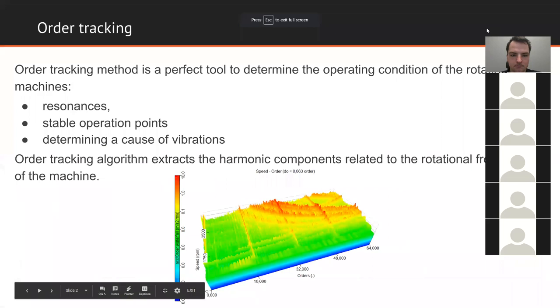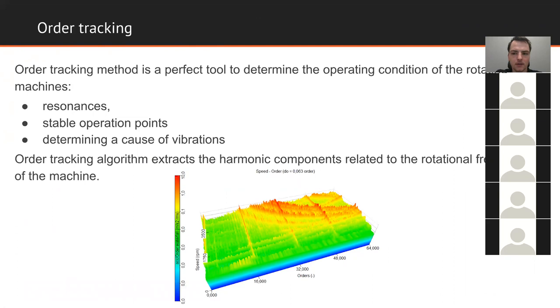Order tracking is a perfect tool to determine the operating conditions of rotating machines — like resonances, stable operating points, and determining the cause of vibrations. It's extremely powerful in combination with other math modules like torsional, combustion, or power analysis. We use the order tracking method to extract the harmonic components related to the rotational frequency of the machine by transforming a measured signal from the time domain to the angular or order domain.